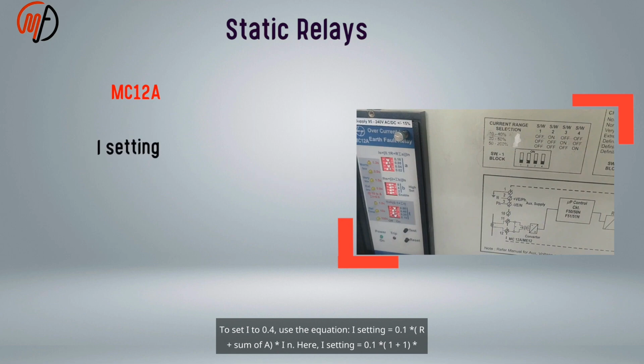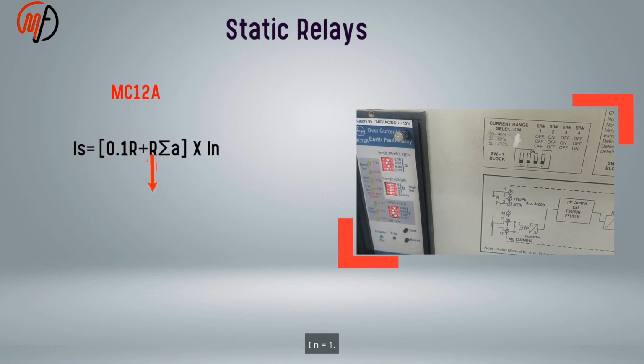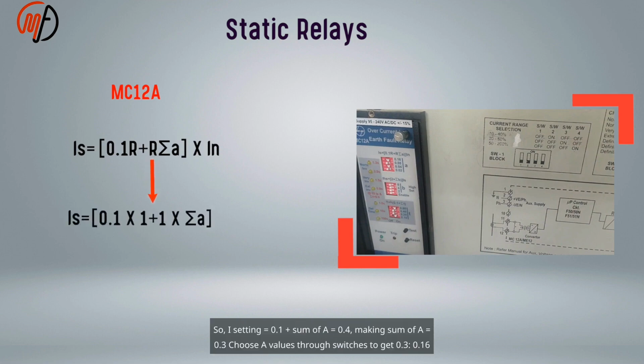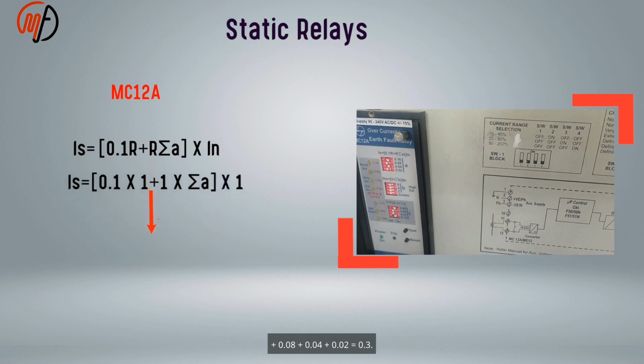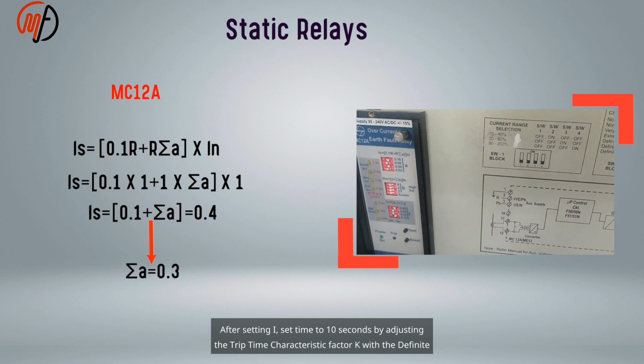To set I to 0.4, use the equation: I setting = 0.1 R plus R times the sum of A, times IN. Here, R is 1. So I setting = 0.1 plus the sum of A = 0.4, making the sum of A = 0.3. Choose the values through the switches to get 0.3: 0.16 plus 0.08 plus 0.04 plus 0.02 equals 0.3. Move these switches right to achieve 0.3.